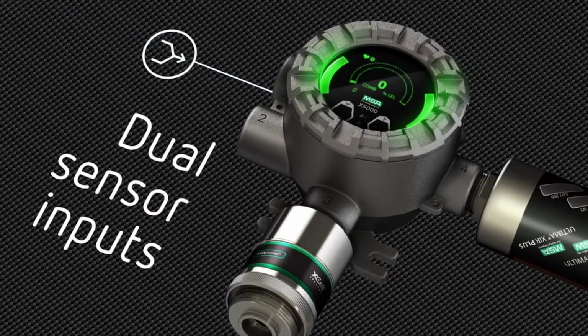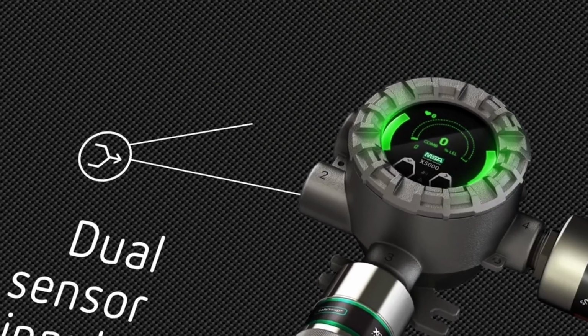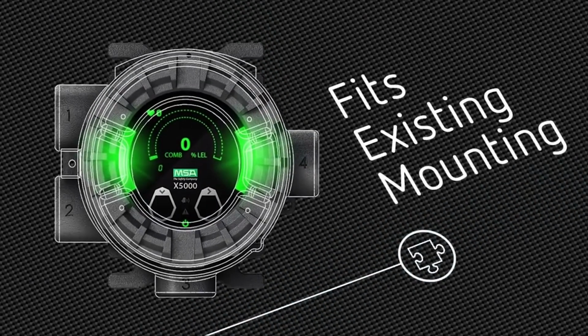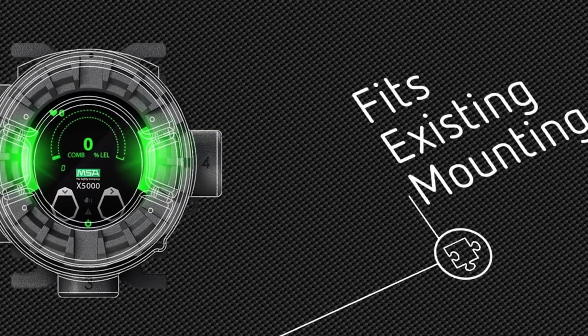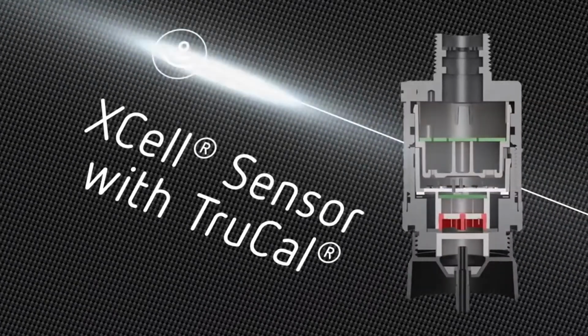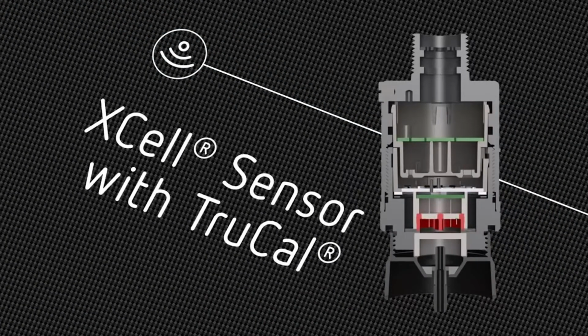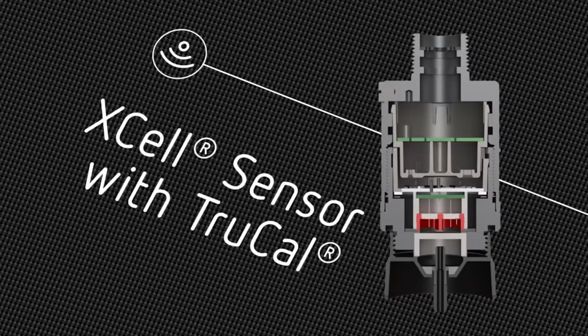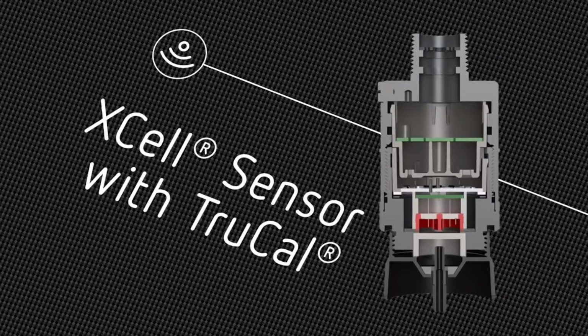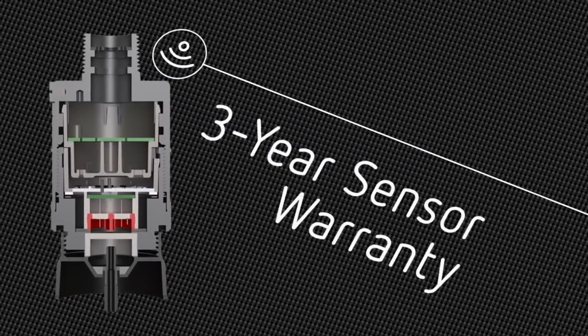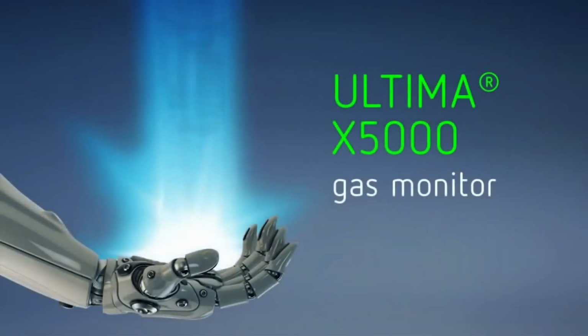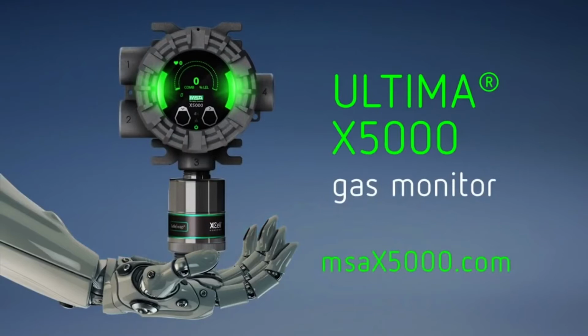Do more with less. Two sensor inputs reduce cost of ownership and double the sensing power. Sensors can be remotely mounted, mixed and matched to suit your gas detection needs. An identical mounting footprint to the Ultima X allows use of existing wiring and conduit, saving you time and money. New advanced XCell sensor technology with TruCal redefines reliability. This innovative technology compensates for environmental shift and sensor drift, extending calibration cycles up to 18 months. Let us cut your maintenance costs in half with a 3-year sensor warranty and a 5-year expected life. A revolutionary gas detector that provides peace of mind. Recalibrate your expectations. The Ultima X5000. Welcome to the future of gas detection.